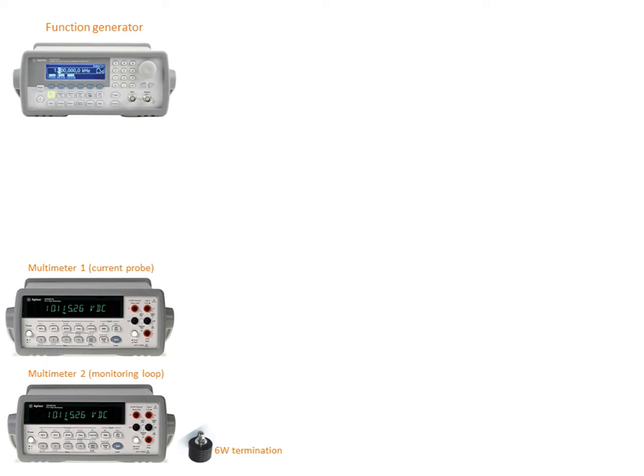The first multimeter is used to read the information coming from a current probe while the second multimeter is used to measure the signal coming from the monitoring loop. For this second device we also need a 6 Watt termination.